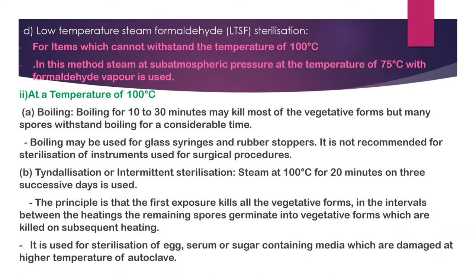Tyndallization, or intermittent sterilization, uses steam at 100°C for 20 minutes on three successive days. The principle: the first exposure kills all vegetative forms; in the intervals between heatings, remaining spores germinate into vegetative forms, which are then killed on subsequent heating. It is used for sterilization of egg- or sugar-containing media damaged at autoclave temperatures.